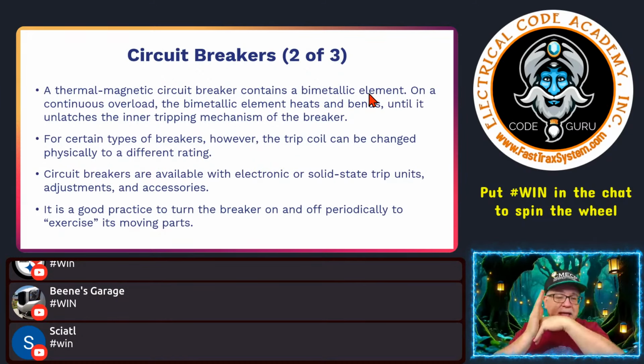So that's a mechanical mechanism. It actually holds it, and as the heat builds up, you're overloading it. It will slowly bend, and then guess what? It trips. So that's a thermomagnetic circuit breaker. On a continuous overload, the bimetal element heats and bends until it unlatches the inner tripping mechanism of the breaker. Now, for certain types of breakers, however, this trip coil can be changed physically to a different rating. Some of the larger circuit breakers, the ones that you pay a lot of money for, have components that can be interchangeable, so they can change different characteristics of the circuit breaker.